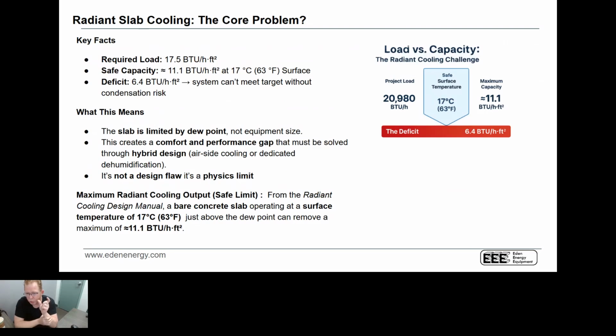And that's where it's really, really important that we understand that if you're delivering 66-degree water into the floor to try to cool the floor, you can remove the sensible heat out of the floor, roughly 11 BTUs per square foot. But if you need 17 BTUs per square foot, we need to understand how we're going to do that. And it's not really a design flaw, it's more of a physics limit, right? If we can reduce the humidity in the space, it also means that we can drop the temperature of the water without causing condensation on the floor. And it's not difficult to do.